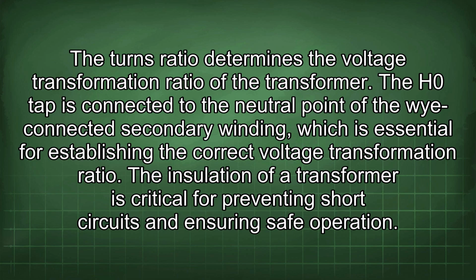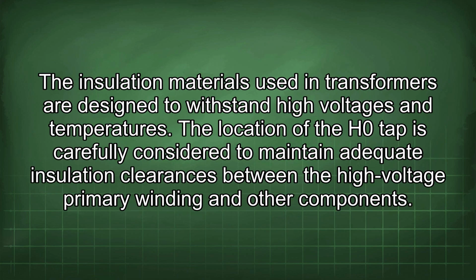The H0 tap is connected to the neutral point of the Y-connected secondary winding, which is essential for establishing the correct voltage transformation ratio. The insulation of a transformer is critical for preventing short circuits and ensuring safe operation. The insulation materials used in transformers are designed to withstand high voltages and temperatures.